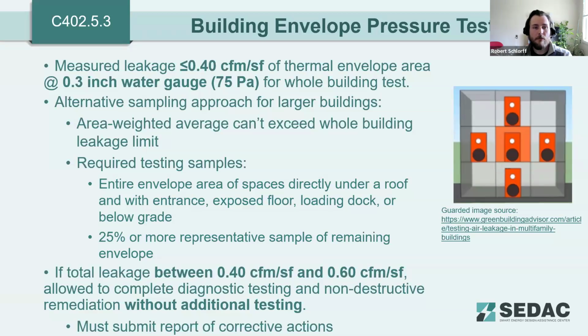There is an alternative sampling approach for a large building. So we're talking about high rises here, or potentially other large buildings that have unusual volumes where it would be difficult to test the whole building. In that case, you can test sample portions of the building on an area weighted average basis that can't exceed the whole building leakage limit.